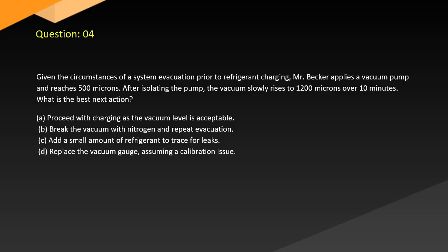A. Proceed with charging as the vacuum level is acceptable. B. Break the vacuum with nitrogen and repeat evacuation. C. Add a small amount of refrigerant to trace for leaks. D. Replace the vacuum gauge, assuming a calibration issue.